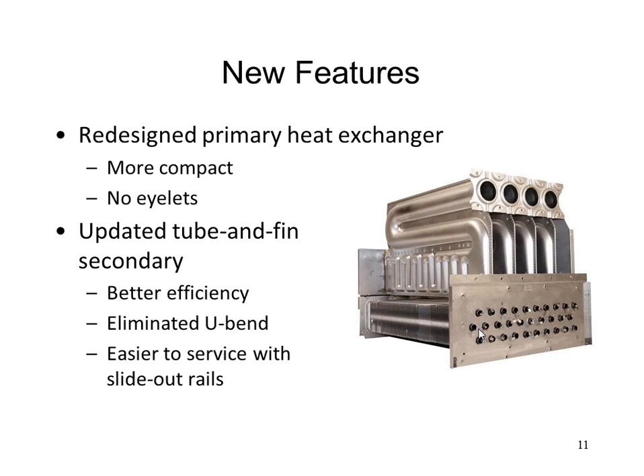There are multiple reasons for the new secondary heat exchanger. One of the main reasons is the height, to get the furnace to be 5 inches shorter, and to improve the efficiency of the furnaces. We couldn't just make it shorter because that would give us a smaller heat exchanger, which would reduce our efficiency. So we need more surface area. So to get that surface area, we went to a fin and tube type design. So it gives us more efficiency and a shorter furnace.